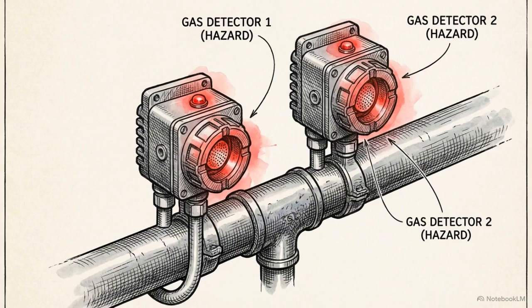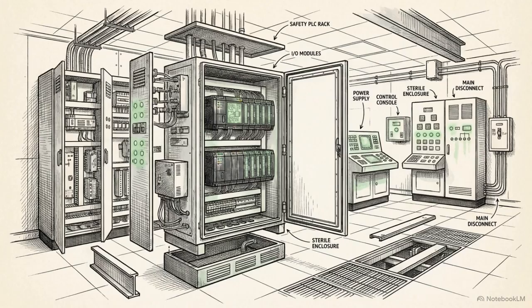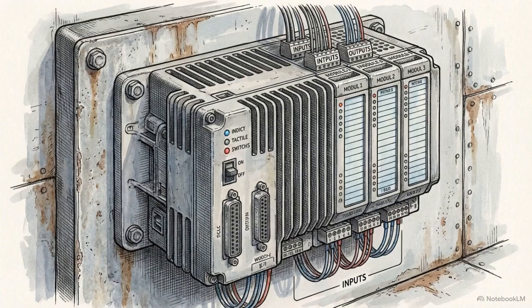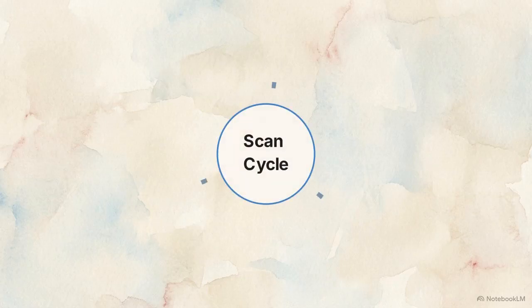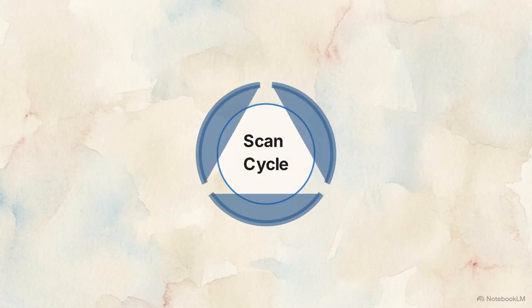With the 2 out of n signal confirmed, data travels to the safety logic solver, a dedicated piece of hardware known as a programmable logic controller, or PLC. Unlike a consumer computer, an industrial PLC is ruggedized to survive severe vibration, extreme temperatures, and heavy electrical noise. The PLC processes information through a 3-step scan cycle.